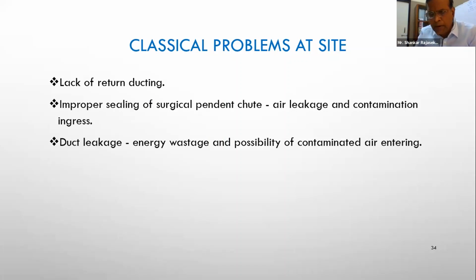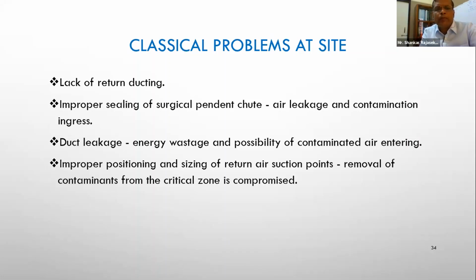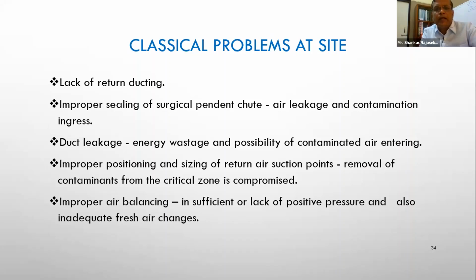Imagine an operating room where you have HEPA filters at the terminal and the duct leaks above the false ceiling. From there, there is every possibility that unfiltered air can infiltrate into the operating room through any gaps or small cracks in the false ceiling at the corners, and thereby the operation theater sterility would be compromised. Improper positioning of return and sizing of return air suction points, improper air balancing.